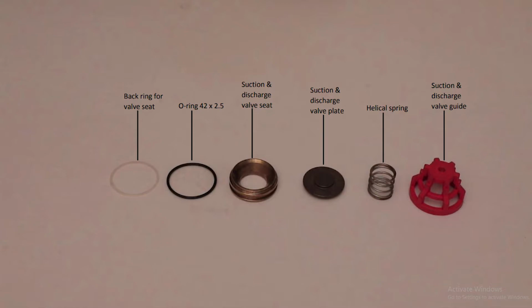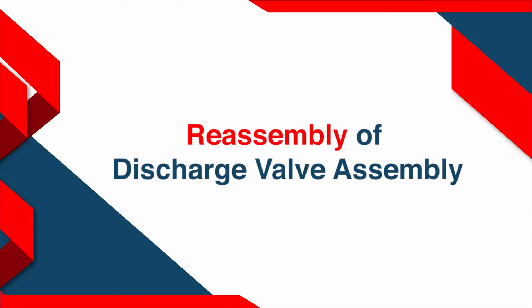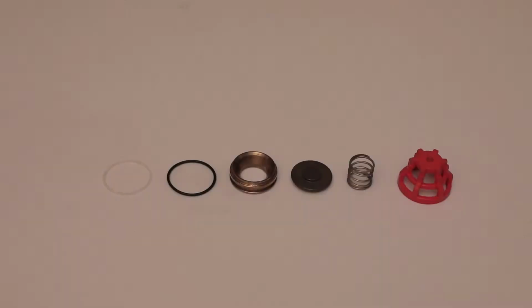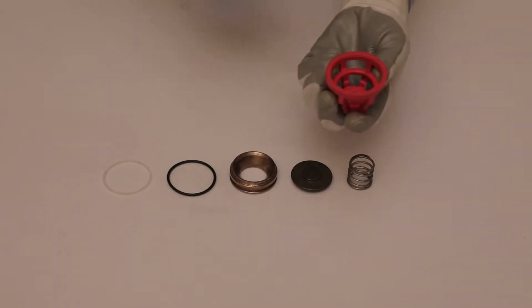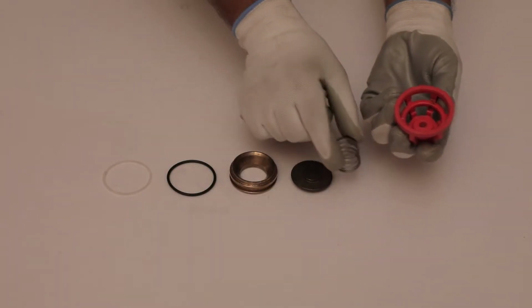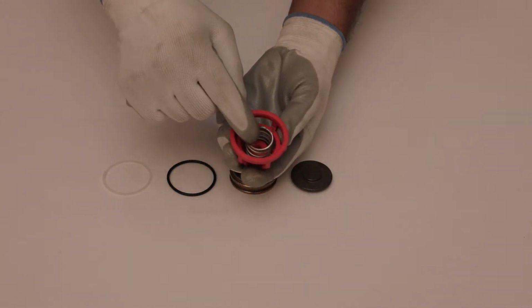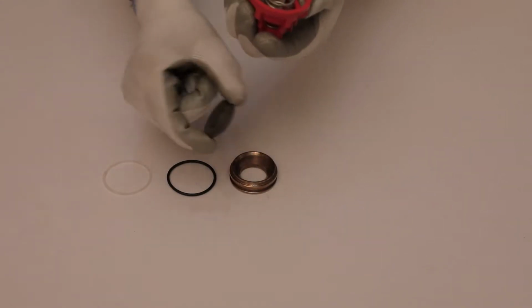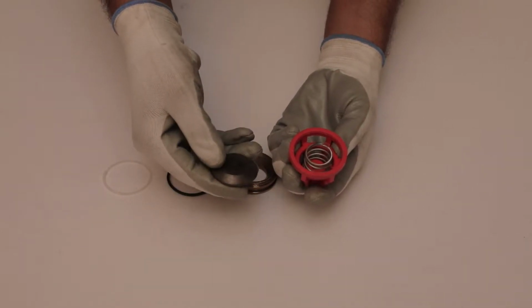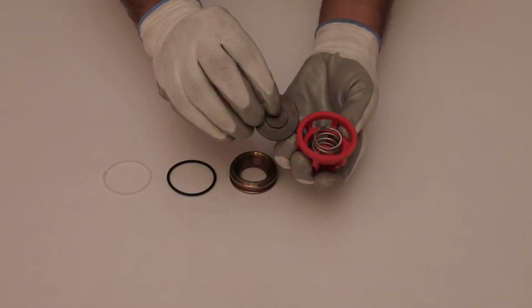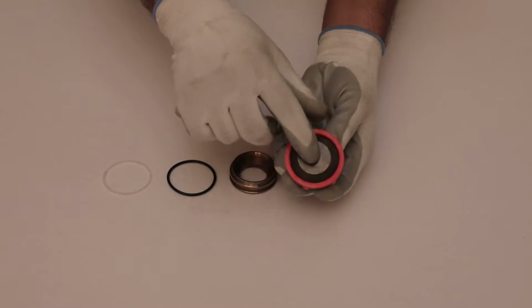Reassembly of discharge valve assembly. Take suction and discharge valve guide and put helical spring into its proper position. Place suction and discharge valve plate on spring such that portion having step will be facing to the spring.